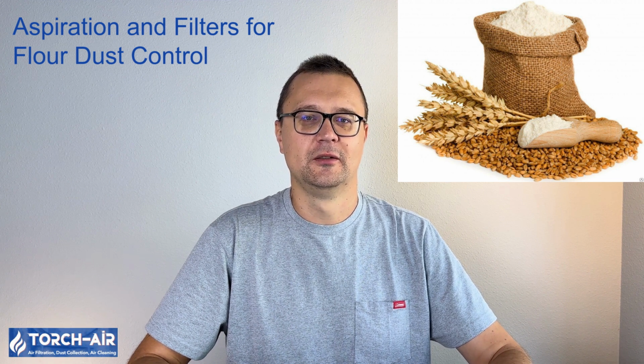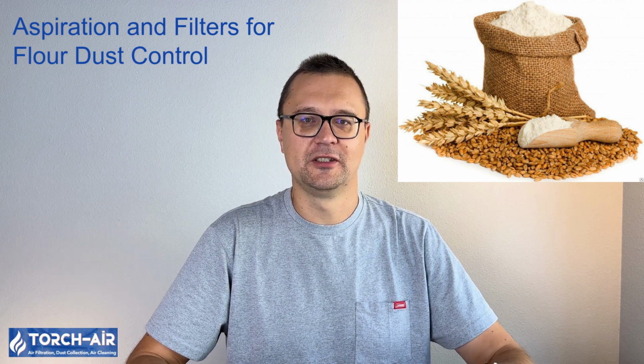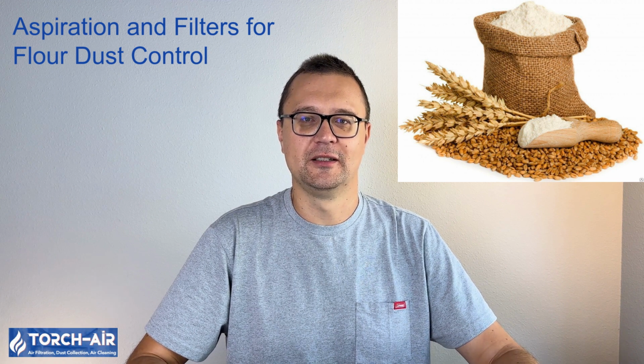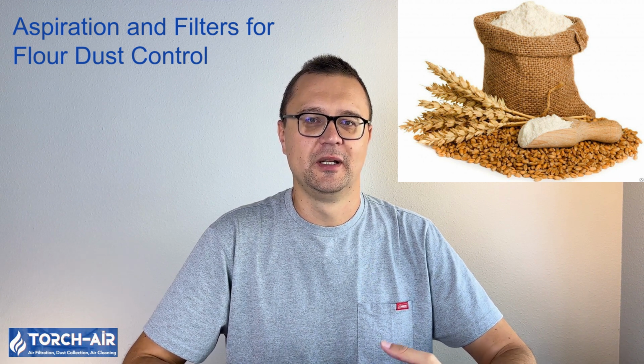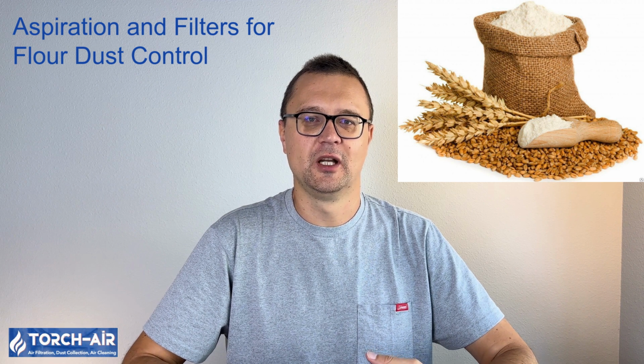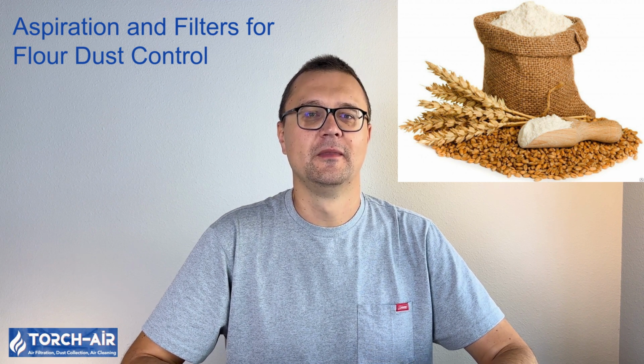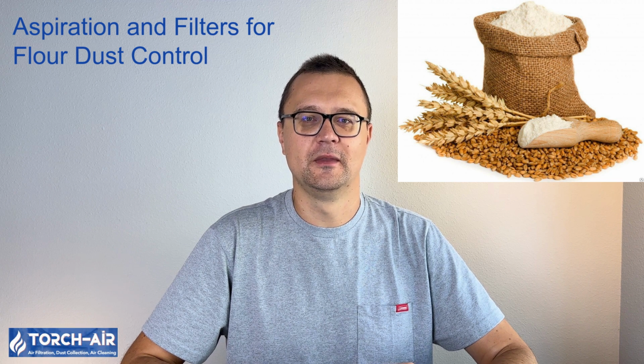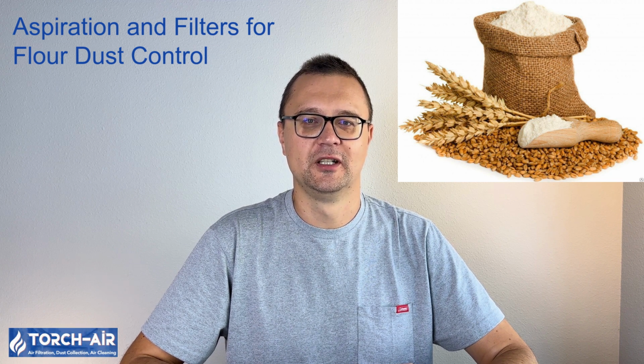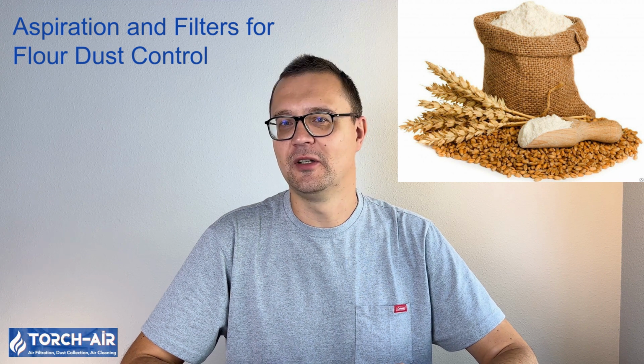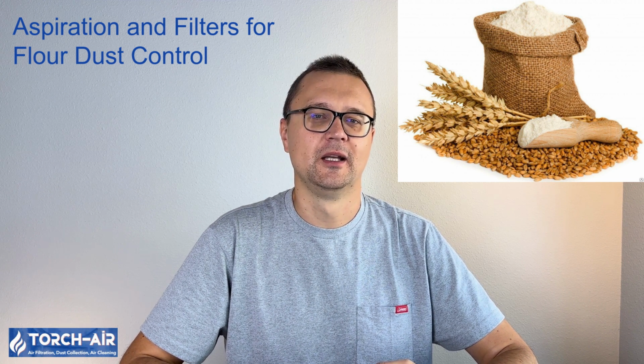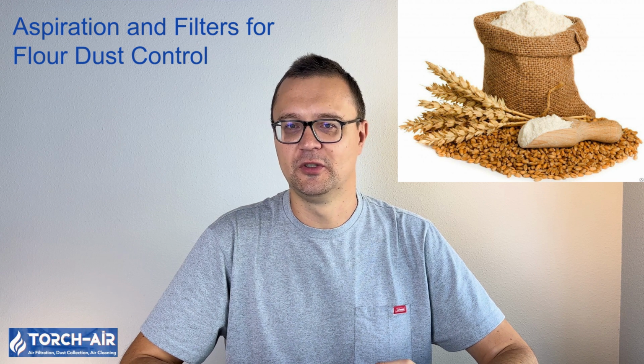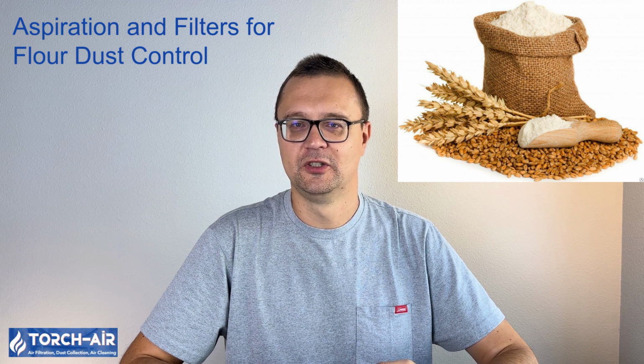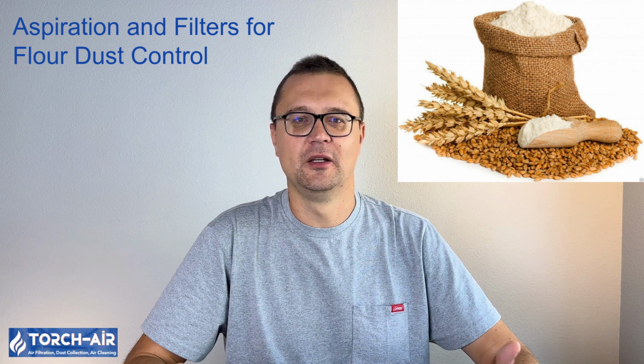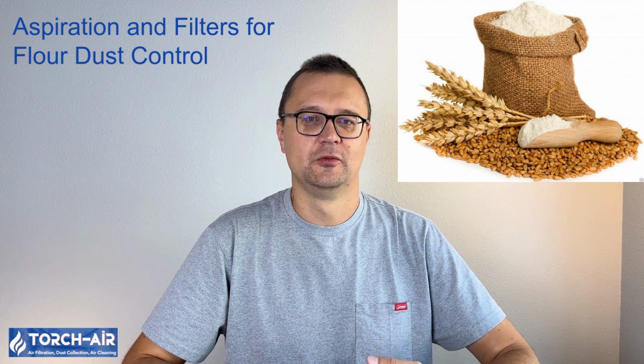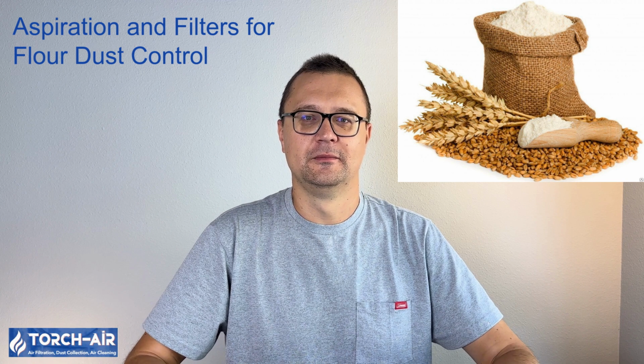Local exhaust ventilation, LEV. LEV systems use strategically placed hoods and vents near dust sources, e.g., mixing stations, conveyors, to capture flour dust as it's generated. Centralized dust collection. In larger facilities, a centralized dust collection system can be installed to handle dust from multiple points of production. Air is pulled through ducts to a central filter where the dust is captured. Enclosed conveyors and equipment. Enclosing conveyors and sifters can help prevent the release of flour dust into the air.